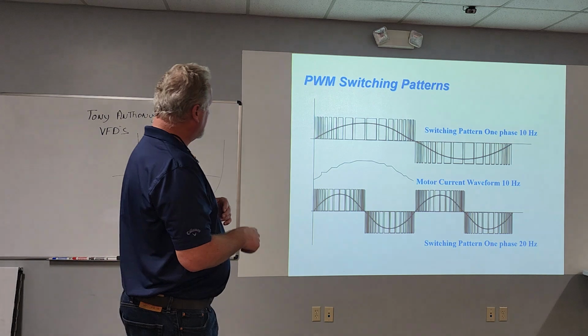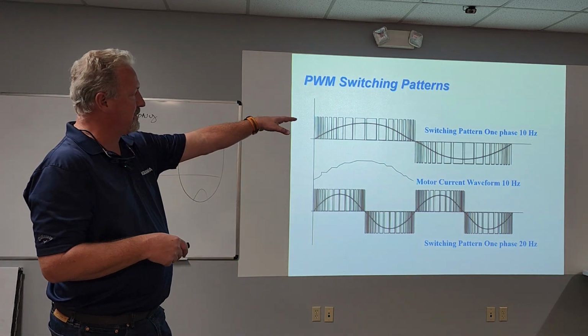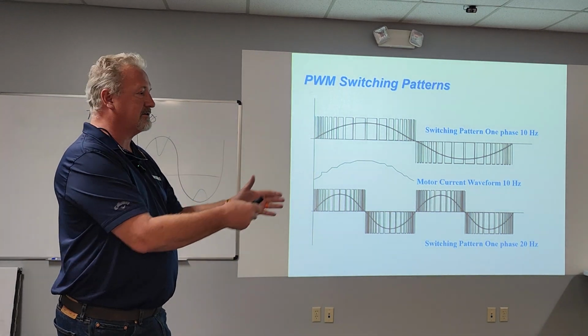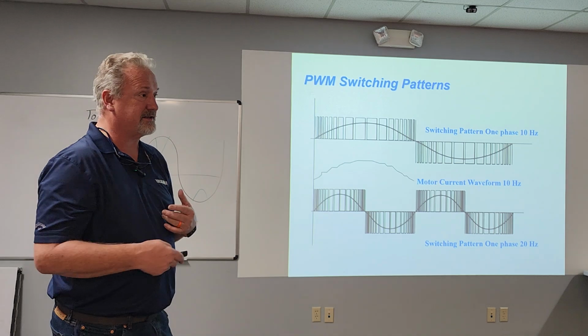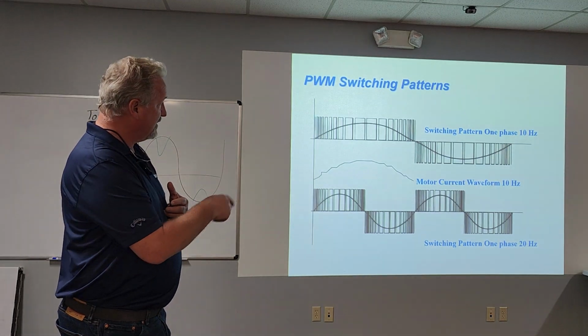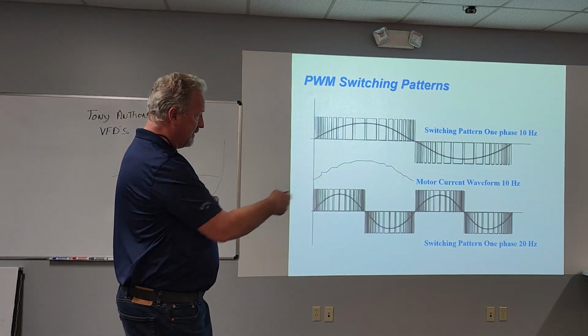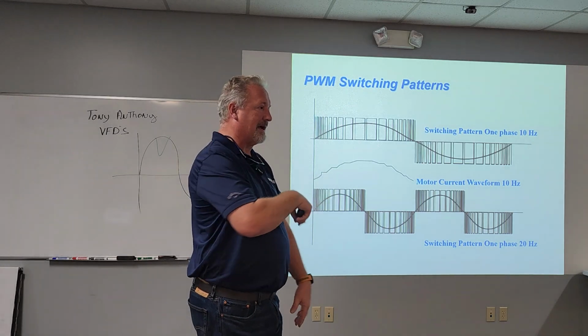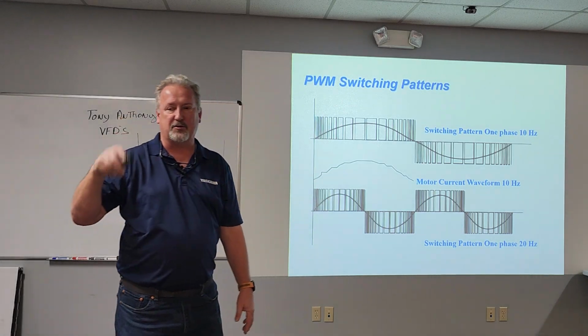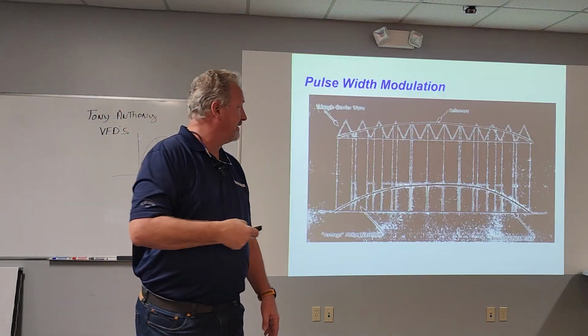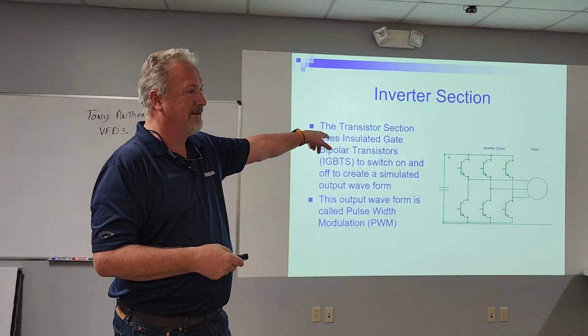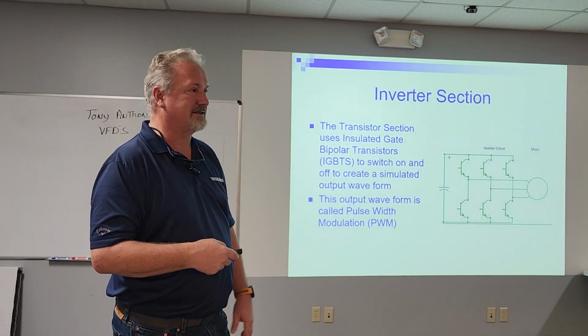So this is what you'll see. We keep hitting these pulses. If this would be like a 10 hertz pattern, so we're running the motor at 10 hertz, which y'all probably never ever see in the HVAC world. We fire that even quicker. Now we're doing 20, and we just keep doing. So this is how we create the AC, by controlling how fast we're firing these IGBTs. These things are getting fired at thousands of times a second.